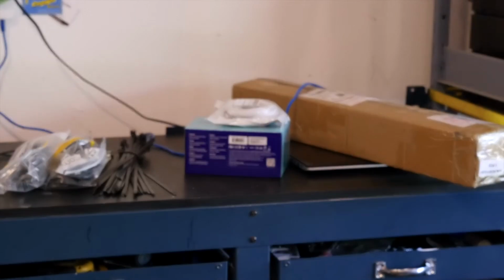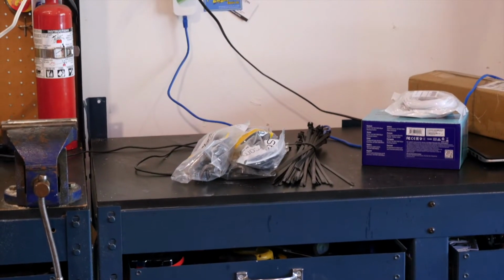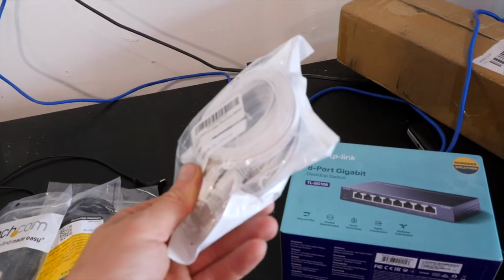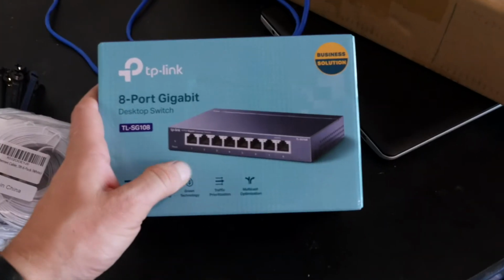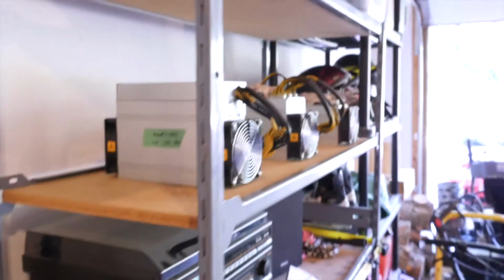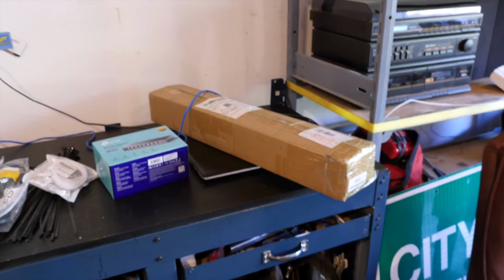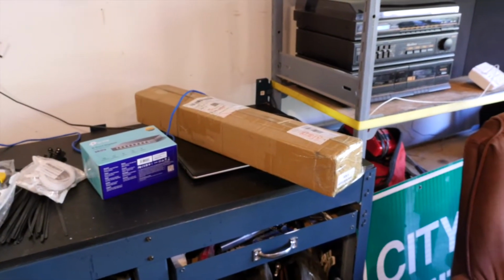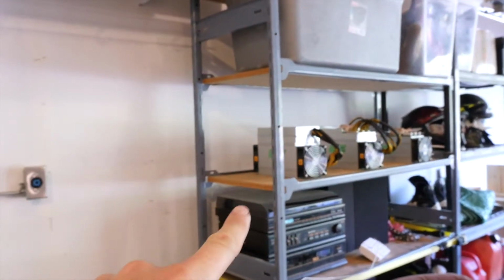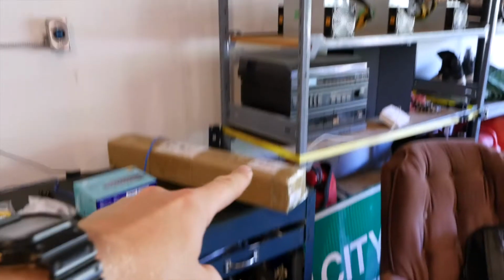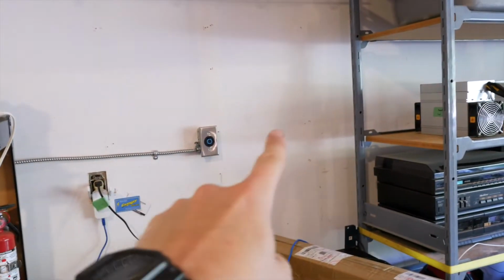I have a few different parts I'm going to put together: some 14 AWG cables, a network switch, some Cat6 Ethernet cables, an 8-port unmanaged network switch. It's just a splitter for Ethernet to go to my miners. I also have a 30 amp 240 volt PDU, which I'm going to hang right here and hook up all my miners onto, so I don't have to have 3 different outlets.